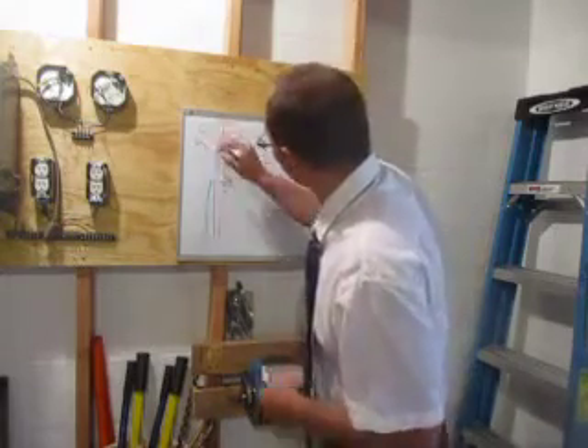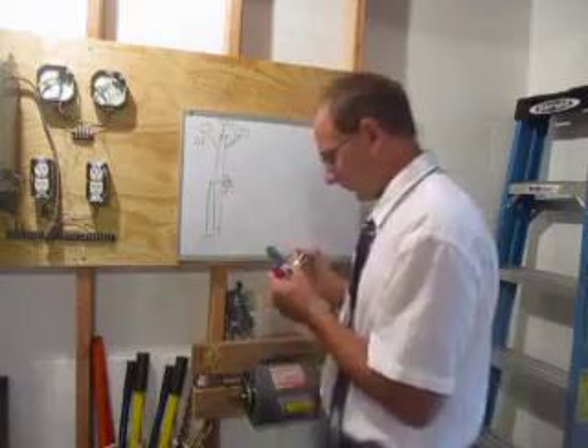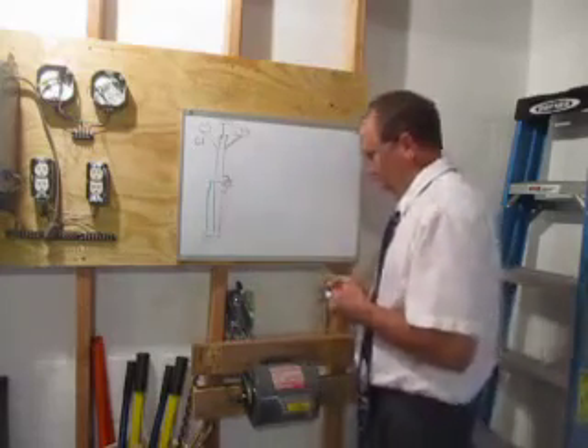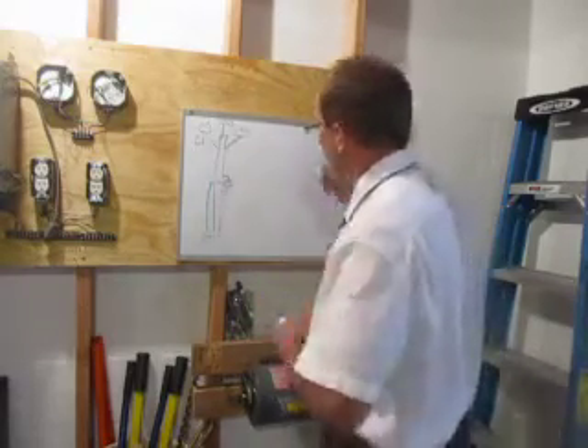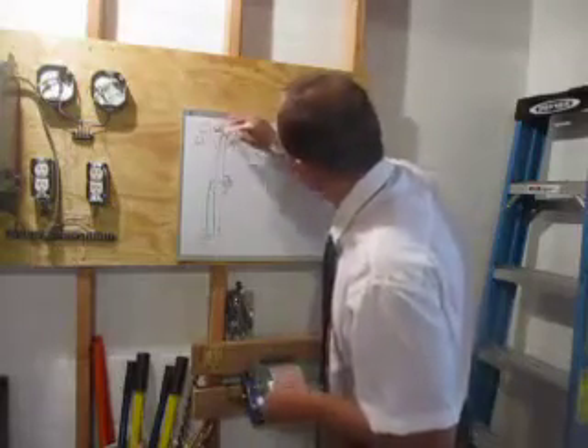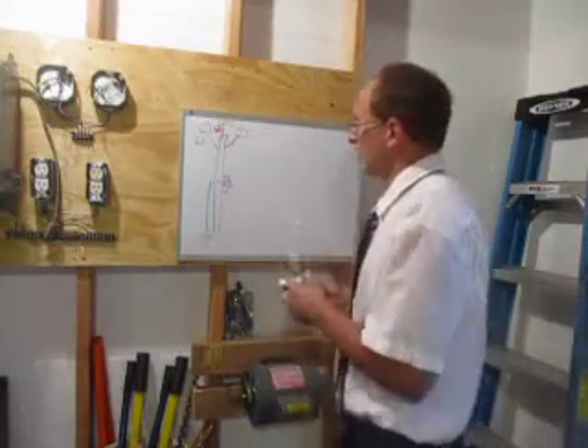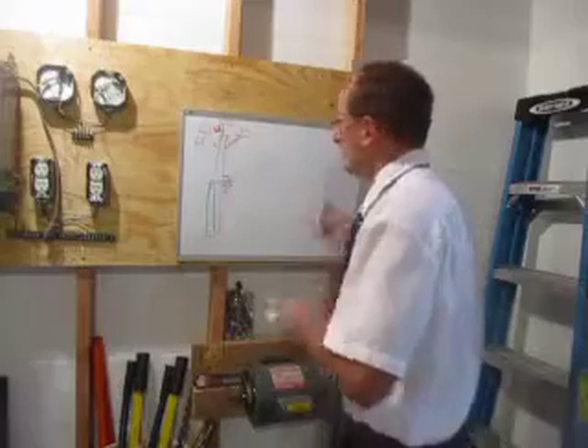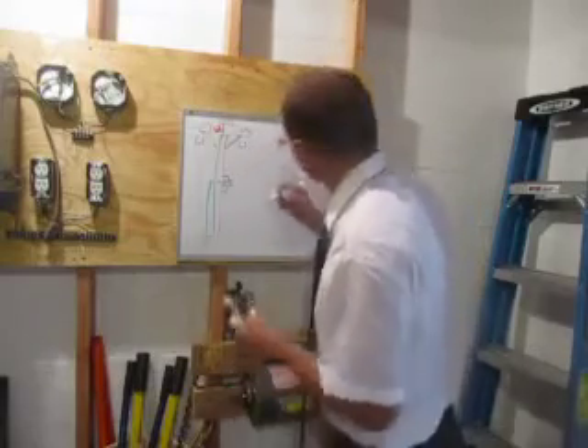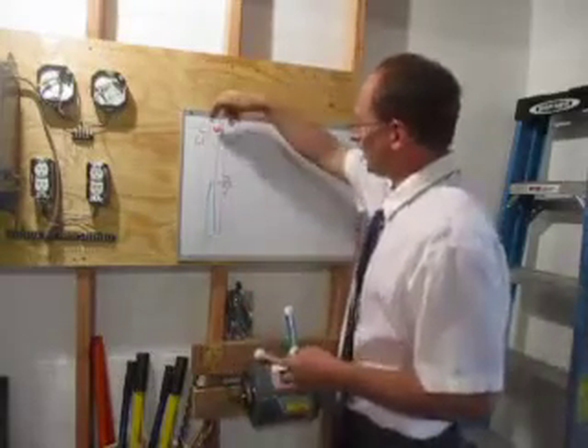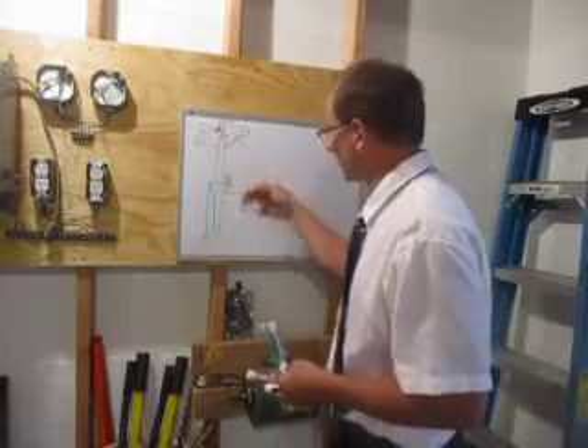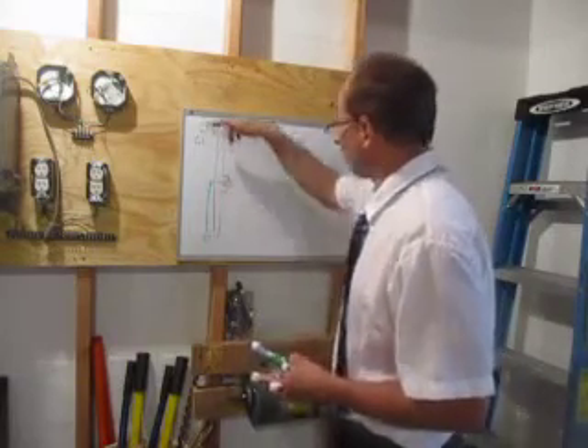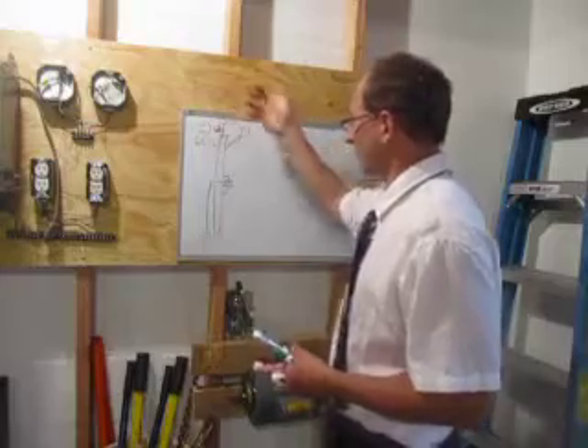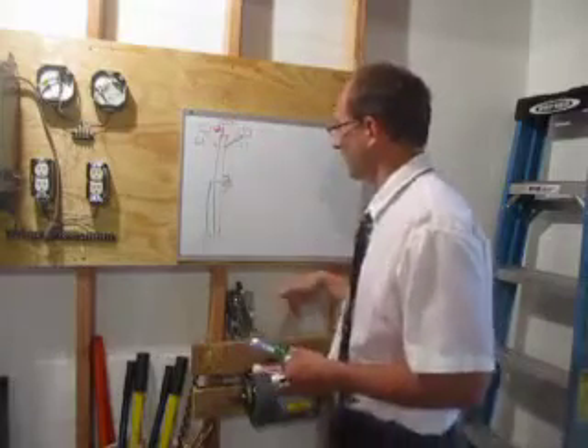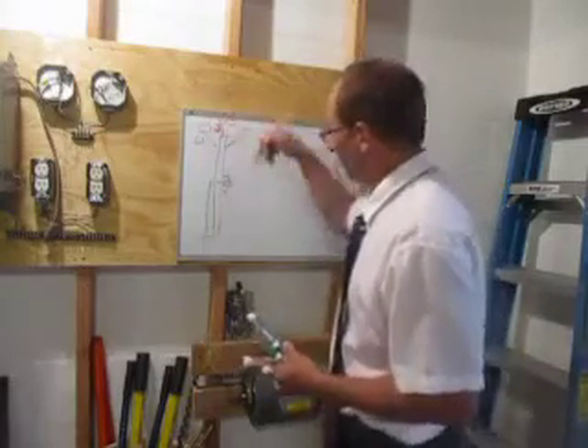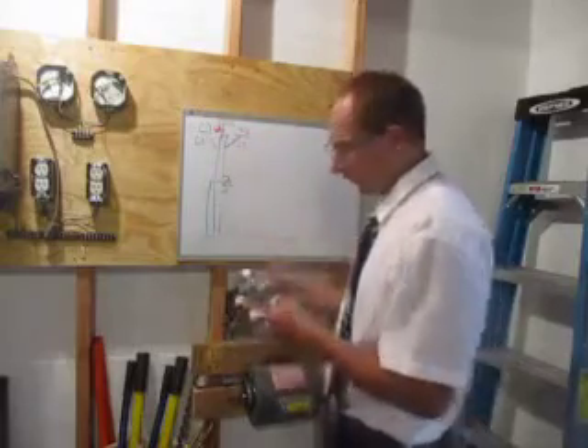you'd have L1. That'll be your 7200/12470. Any one of these conductors to ground is 7200 volts. L2 and L3: black, red, blue. Any one of these to ground or neutral, the grounded conductor. These would be your ungrounded conductors up here because they're live. They touch anything, they catch fire. But any one of these to this neutral is 7200 volts.